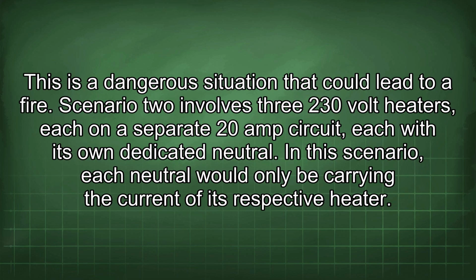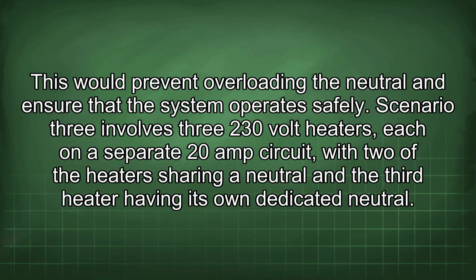This is a dangerous situation that could lead to a fire. Scenario 2 involves three 230-volt heaters, each on a separate 20-amp circuit, each with its own dedicated neutral. In this scenario, each neutral would only be carrying the current of its respective heater. This would prevent overloading the neutral and ensure that the system operates safely.